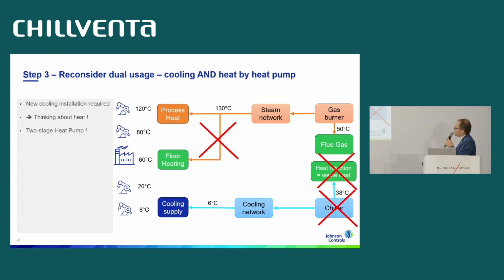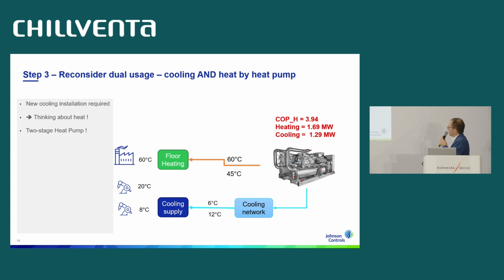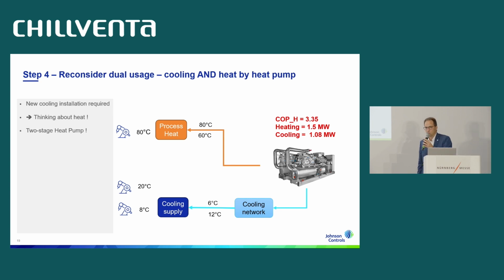Going further is using dual usage. So if you have a possibility to have a new installation and you have process heat demand, think about installation of a dual usage heat pump and cooling. So not simply split again heating by gas burners and cooling by a chiller, but use both. So think about a two-stage heat pump, for example. So this is one of our dual packs serving 6/12 cooling network and also the floor heating at 60 degrees with a really nice COP here. And even this two-stage heat pump is able to provide process heat at higher temperatures, for example 80 degrees. So that's really attractive, and still a very interesting COP heating of 3.35.